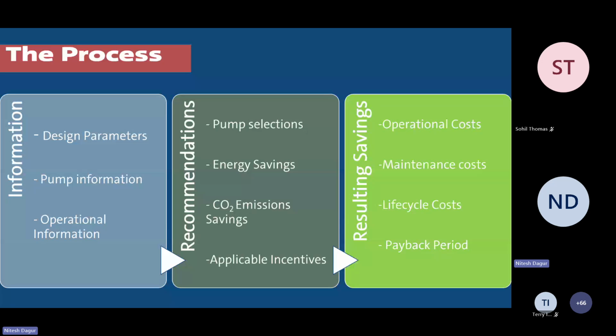In the recommendations, yes, pump selections, of course, the best pumps that we think would be applicable for any given application. The energy savings that will happen if the solution is installed, the carbon dioxide emission savings because of the new equipment, and the applicable incentives, if there are any, depending on where it is being installed. Like IESO and Save on Energy have quite some. I'll be talking about that later on. Based on this, the resulting savings at the client's or end user's operations are in the operational costs, the maintenance costs, and the life cycle costs of the whole pump, basically.